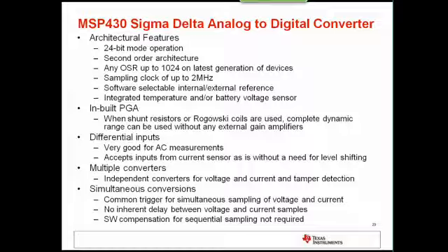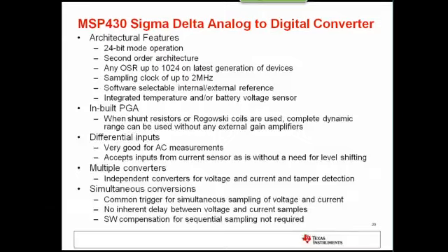The oversampling ratio on the Sigma Delta can be up to 1024, and the modulation clock can be up to 2 megahertz. There's also software selectable internal or external reference, integrated temperature and/or battery voltage. Another feature is a built-in programmable gain amplifier, which magnifies the output of low voltage current sensors such as shunts and Rogowski coils. The Sigma Deltas also have differential inputs, which is good for AC measurements, eliminating the need for a level shifter and simplifying the analog front-end circuitry.